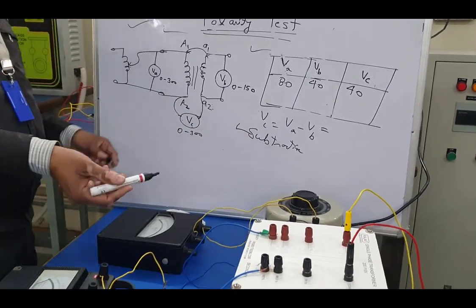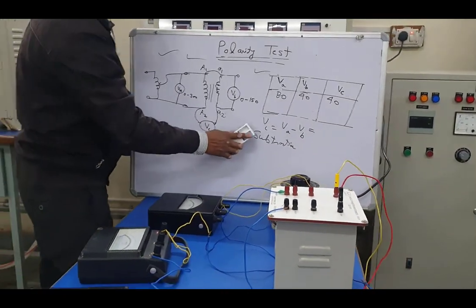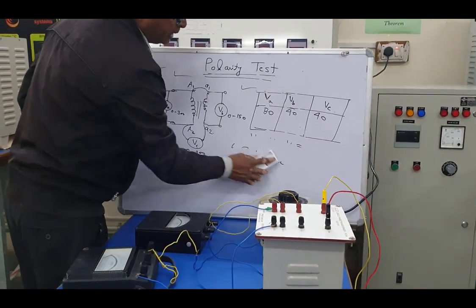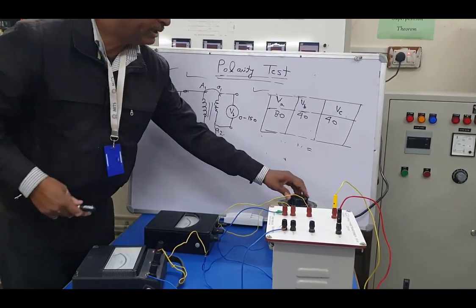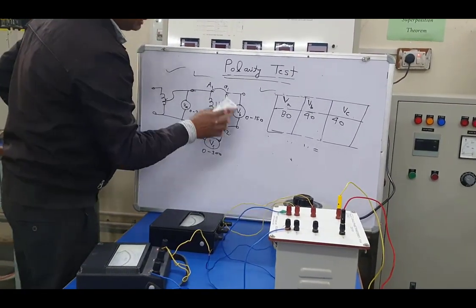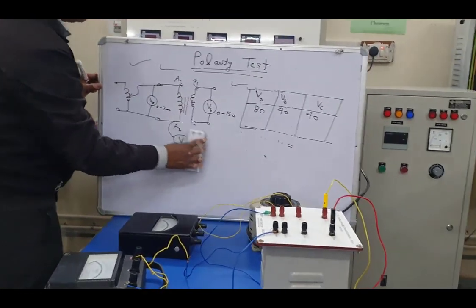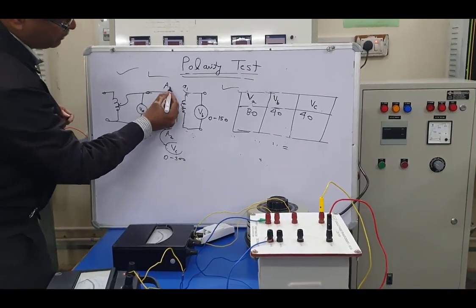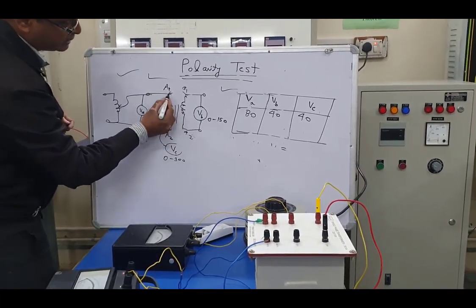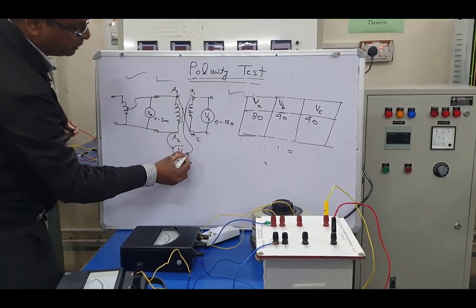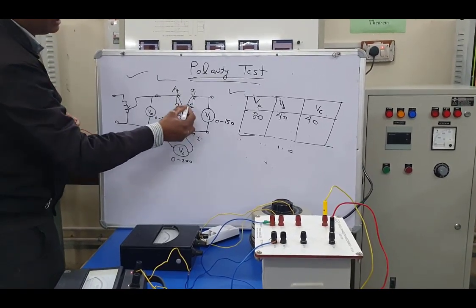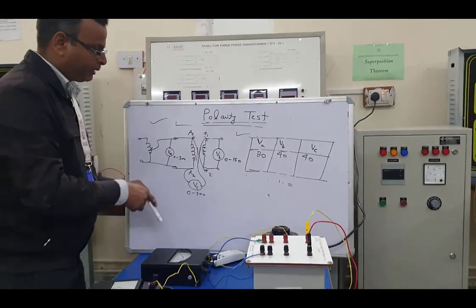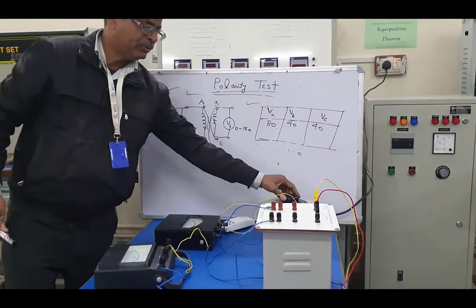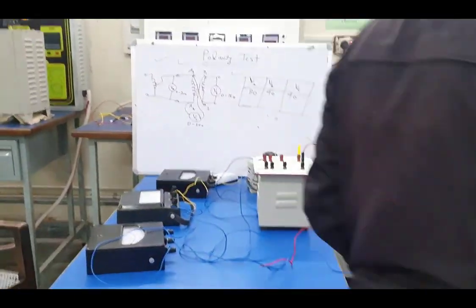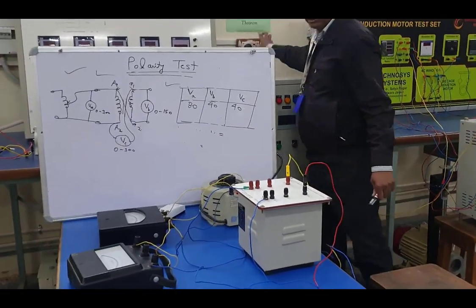Now for the second part of this test, we have to find the additive polarity. So for additive polarity, first of all we reduce the voltage and interchange the terminals. Interchanging the terminals means this one terminal connects to small a2 and this small a1 connects to the voltmeter. And this circuit diagram we have to apply on this transformer. But before this we switch off and interchange the terminals.